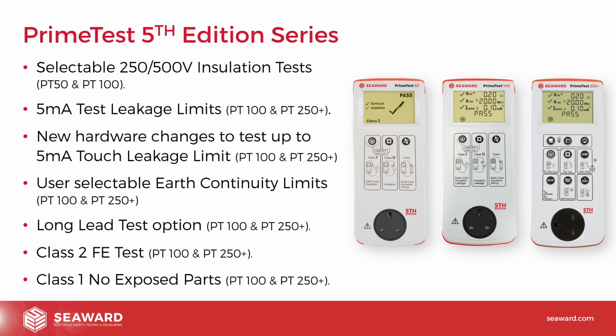So we've had to make changes, particularly for the touch current, to make it measure all the way up to 5 milliamps. We've made those changes to the Prime Test 100 and the Prime Test 250 Plus. There's no leakage test option on the 50, so that's why we didn't include it on that.